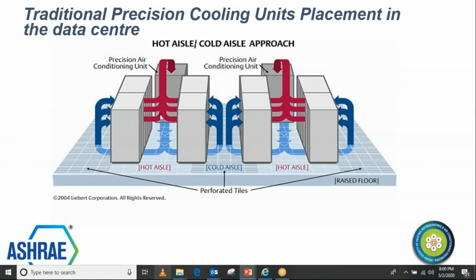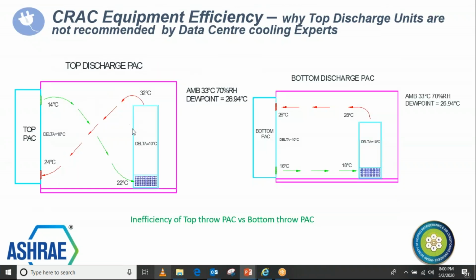Obviously there could be different types of servers and switches designed. Sometimes servers may discharge hot air from the top, and some switches discharge even from the sides, but we should try to use these kinds of systems. So what happens when we use top discharge units in applications where the equipment is sucking cold air from the bottom or from the bottom front? Suppose this is the equipment you want to cool, sucking cold air from the bottom front. Imagine this is your cooling unit, discharging cold air from the top through a duct or a direct plenum or whatever way, and the suction return is from the bottom front of the cooling unit. So you are throwing cold air from the top like this, and sucking the hot air like this.